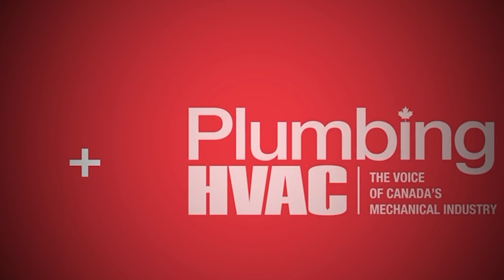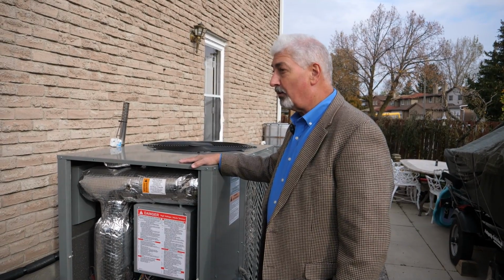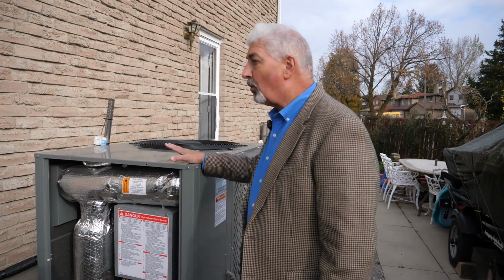Is there anything you guys have put into this design to try to keep the noise level down comparable to an electric heat pump? Well, we've designed some of the piping around the solution pump to mitigate any kind of sound issues. We've designed the air handling indoors to mitigate sound issues. But a couple things you need to know about this is, first of all, like I said before, it's 4-to-1 modulated. So when it's out running at 25%, it's even more quiet than this.